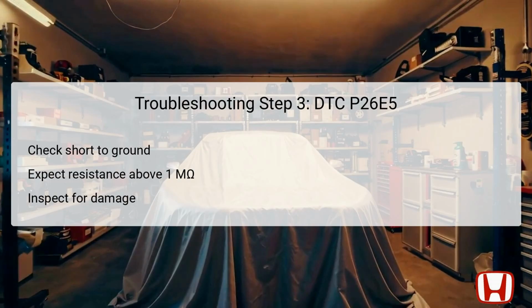In this instance, the resistance should ideally measure more than 1 megaohm. A reading below this threshold suggests a possible short circuit, which can cause significant operational issues in the starter cut relay's function. Inspect for damage along the wire, such as abrasions or corrosion that may lead to grounding issues. Such shorts can cause unintended engagement or failures, affecting engine startup capabilities. With thorough inspections, technicians can help restore relay operations back to standard working conditions.